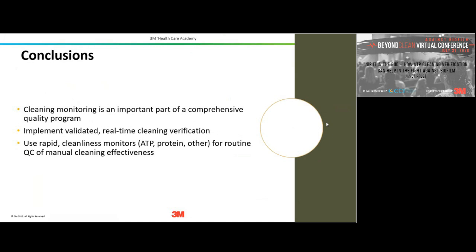Q&A: At what point in endoscope reprocessing do you perform the ATP test? It's done after the manual cleaning step — after manual cleaning and leak testing, when you're ready to take the endoscope to the endoscopy processor or ready to dry it before sterilization. On denatured proteins: denatured proteins will be detected by most protein tests, though it depends on the technology. That would be a question for the specific test manufacturer to confirm they've done testing to ensure detection of denatured proteins. But yes, protein tests can detect denatured proteins.